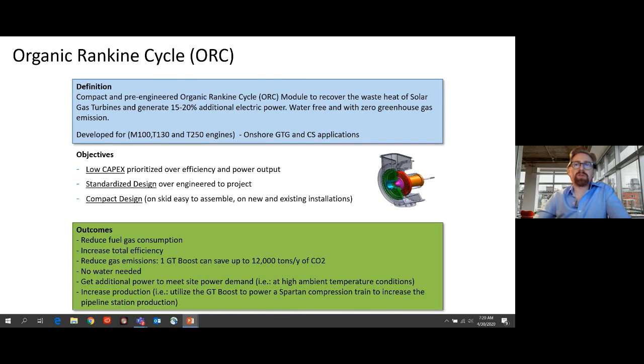When we look at direct versus indirect exchange: with the organic Rankine cycle through direct exchange, we typically just have the gas turbine, then from the exhaust a heat exchanger, and a supplemental turbine extracting additional electrical power, upwards of about 3 megawatts. Again, this is designed for our Titan and Mars product lines, and the advantage is that it's fairly simple in design and doesn't require a lot of additional piping.